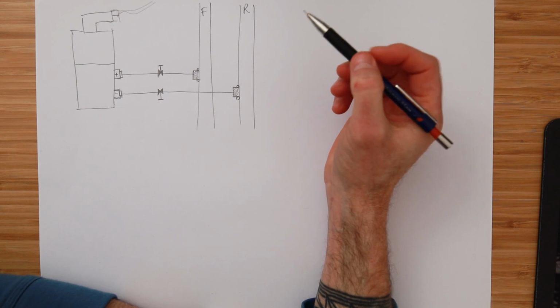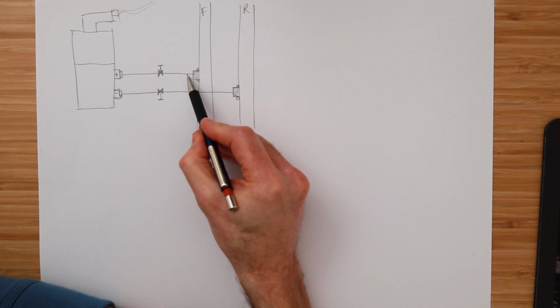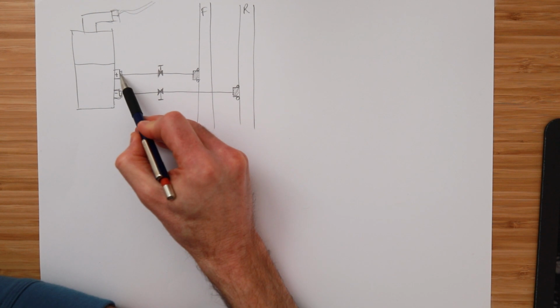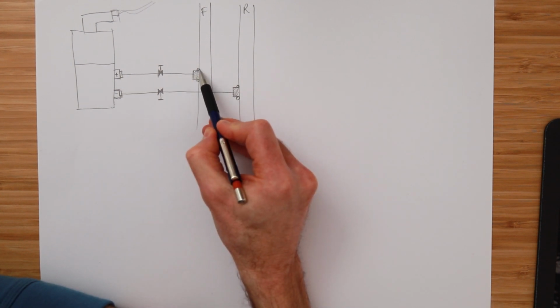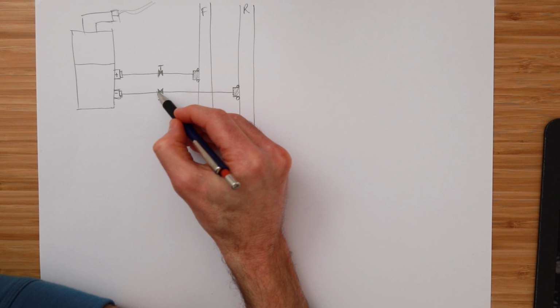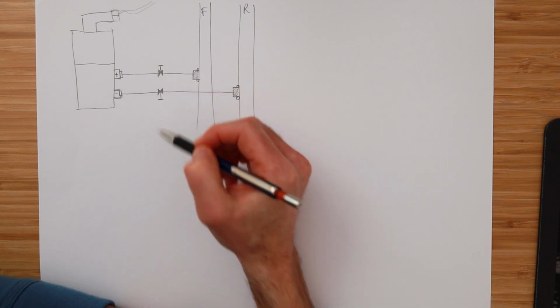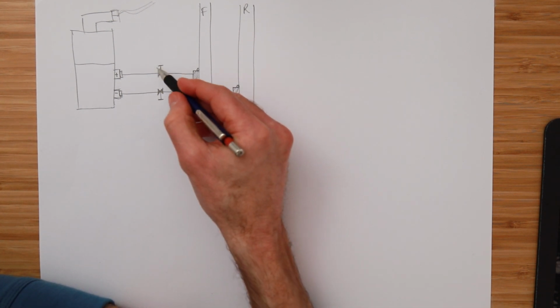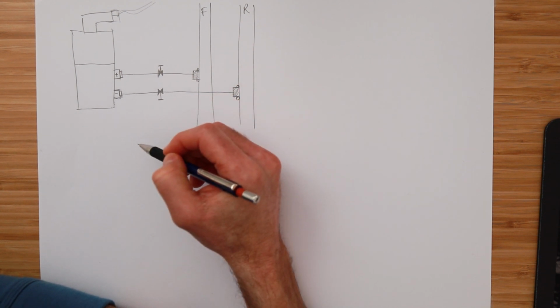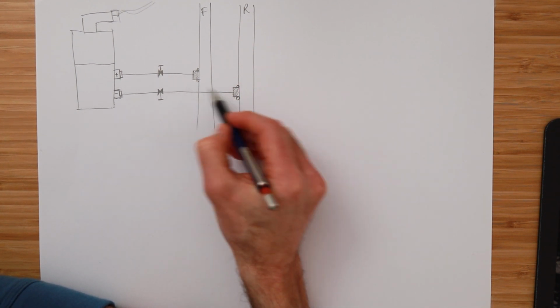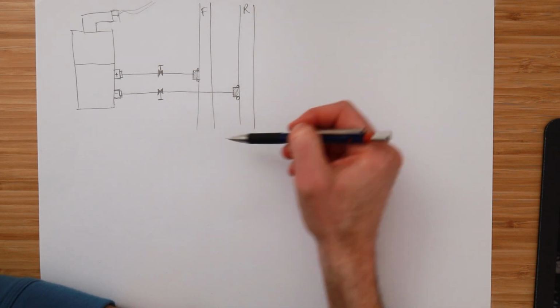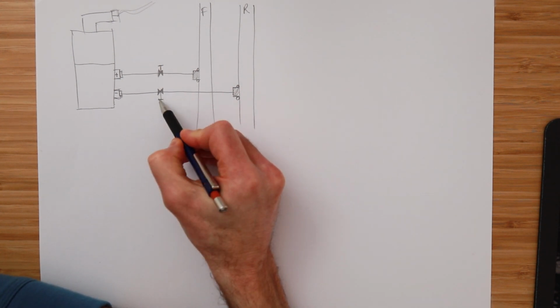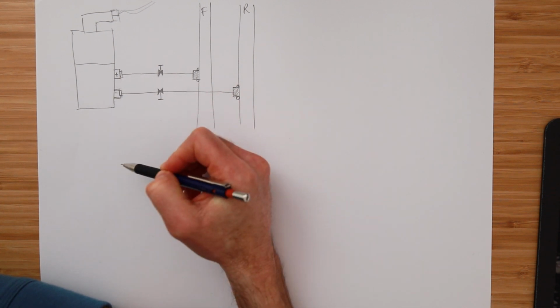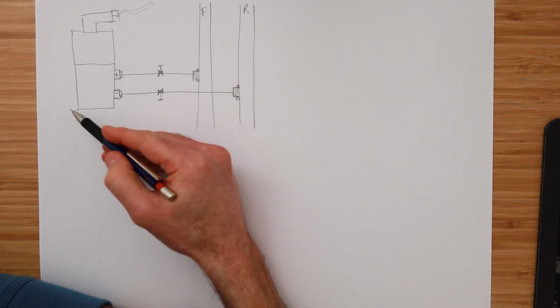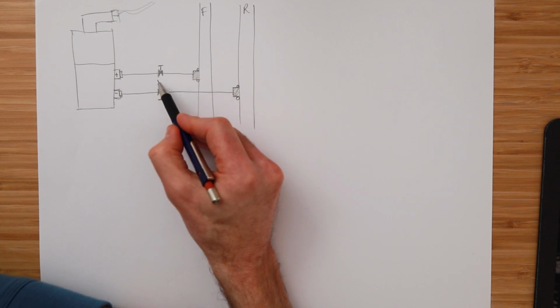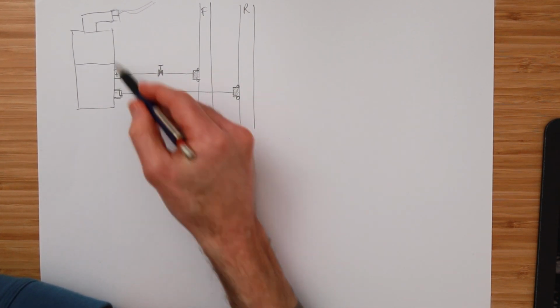So usually when mechanical does this, they've got this sort of 6mm copper tube that runs from the pressure transmitter to the pipe, where they've got the socket welded into the pipe. They will usually provide 2 little manual isolation valves that originally are closed off, and then they'll weld this in and put the pipe in here, and then they fill the water up into the circuit. They will then open these little valves, and it will put pressure onto the transmitter. And obviously if the transmitter fails or there's an issue, you can isolate this and the water is isolated. You can remove this and replace it.